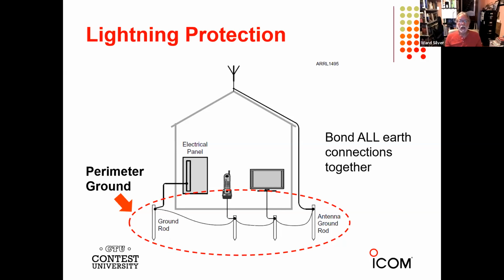Why? If you rely on dirt to connect these ground rods together, what is the resistance of dirt? It's a lot. Okay, so if you get a big lightning surge with hundreds or thousands of amps, and it's going from one ground rod to another through the dirt, say you get 20 ohms and 1,000 amps, that's 20,000 volts between your ground systems. That's why stuff blows up inside your house, even though you didn't see the lightning come in and hit it. Suddenly your AC service ground is 20,000 volts different than your telephone or your computer or your TV. Yeah, there's going to be some damage.